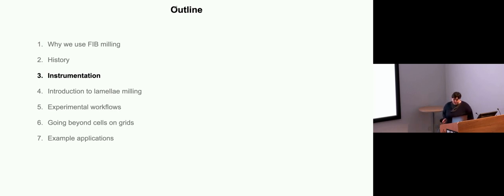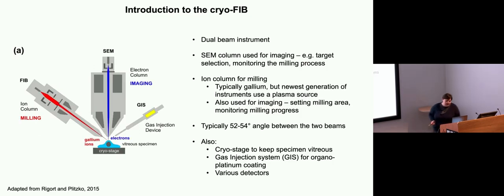Now I've done some basic introduction, I want to move on to talk about the instrumentation. This schematic is a basic overview of what these instruments look like. It's a dual beam, so you have the SEM column and the ion column, and these are approximately 50 degrees angle between them. It depends a little bit on manufacture and specific instrument. The SEM column is there for imaging, the FIB column for milling but also imaging as well.